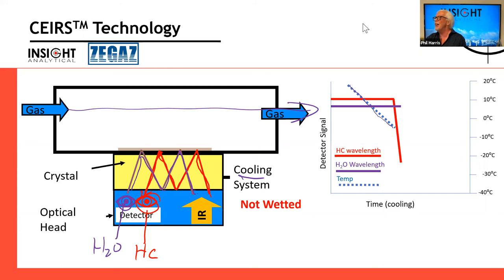Oh, sorry, and you also mentioned integrating with a compact probe with a larger tube diameter, where the sample's not as clean. Yeah, certainly. Actually, we're going to do a talk in about a month from now about some of the products we're developing here. And one of them is a fast loop probe that lets you run a fast loop just using the process flow velocity to create differential pressure. So now you can get a sample flowing out to the analyzer and back, returning to process at full line pressure with no pumps and not having to vent anything. And yeah, you can use a large diameter then, which is going to help you with a dirtier sample for sure.